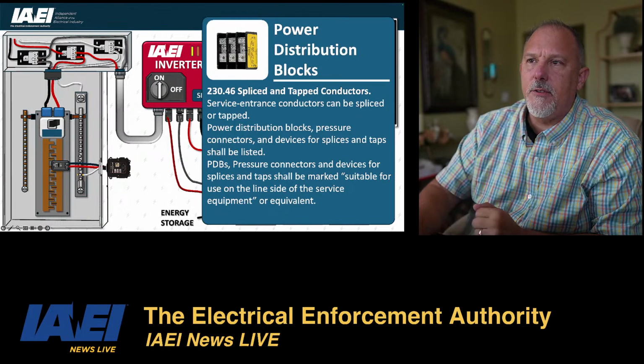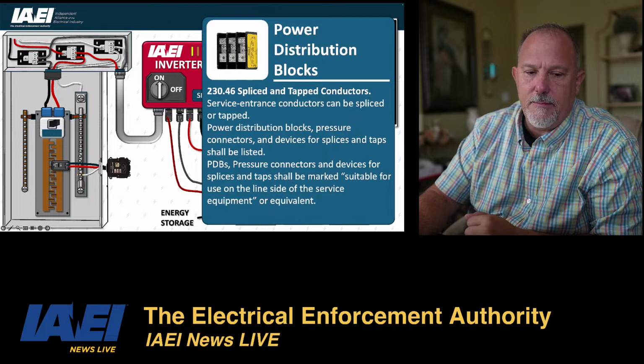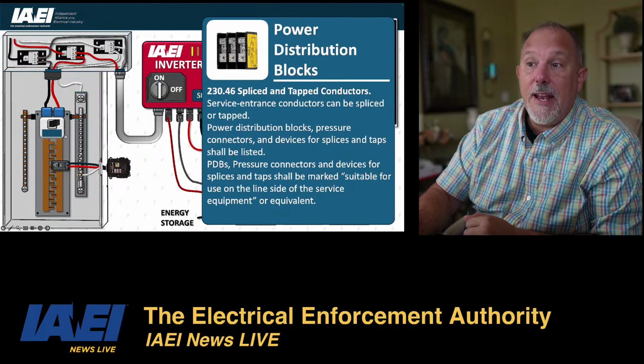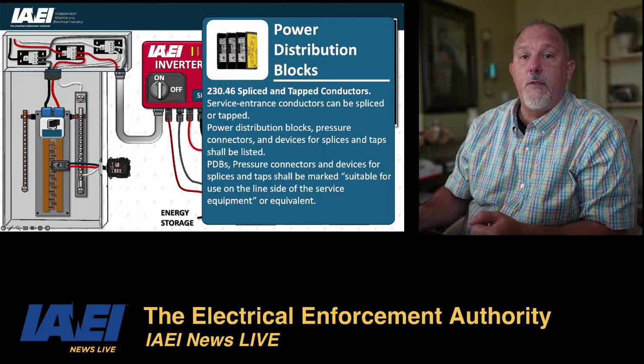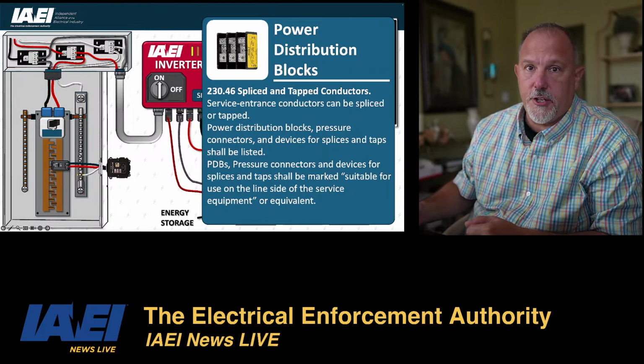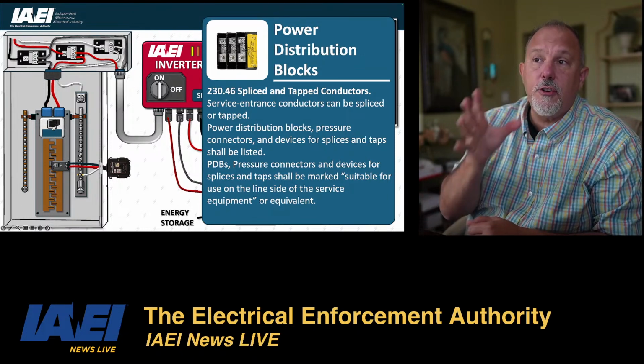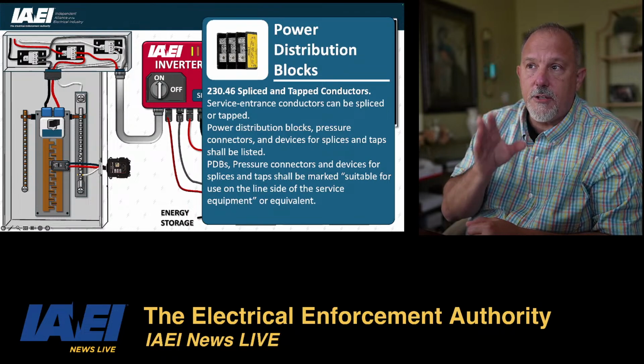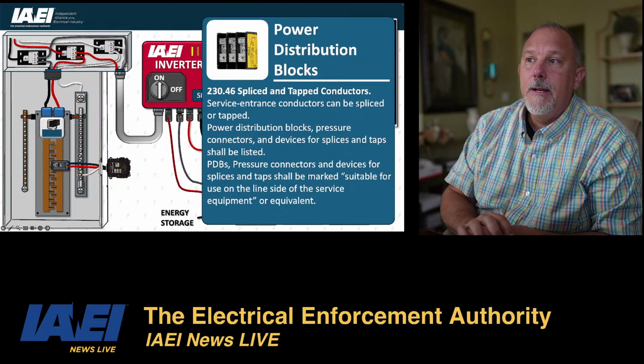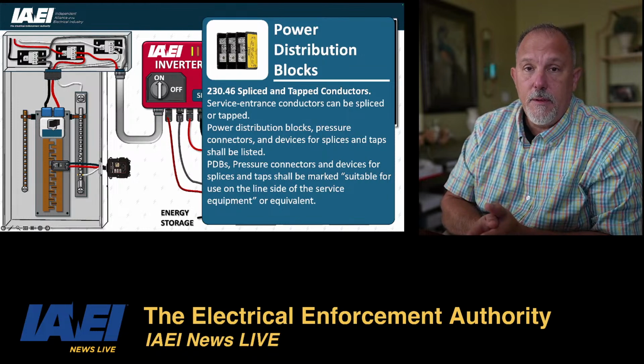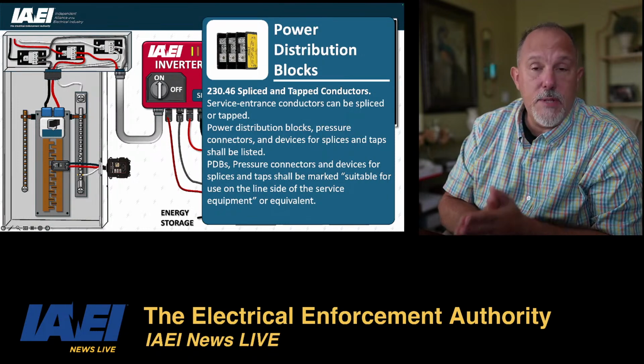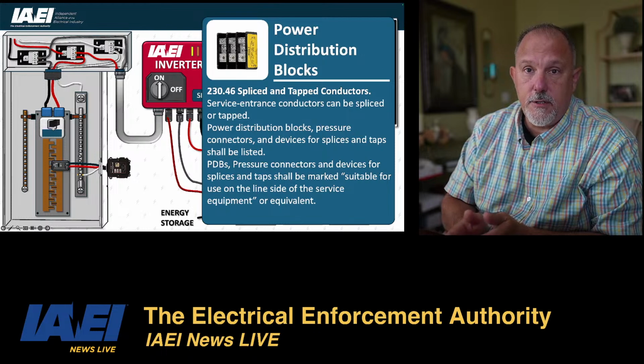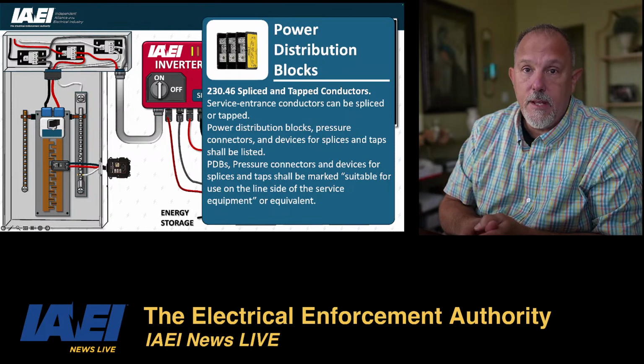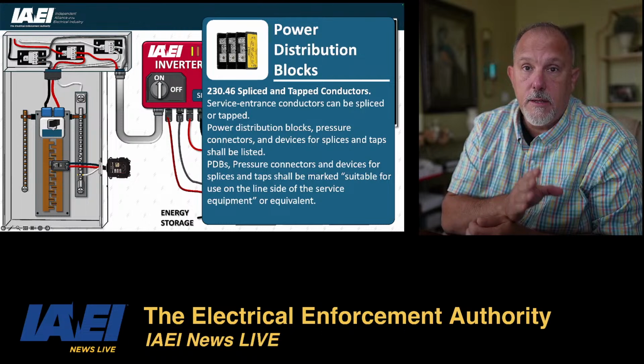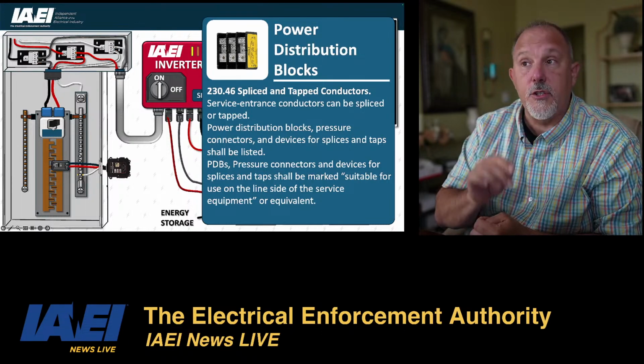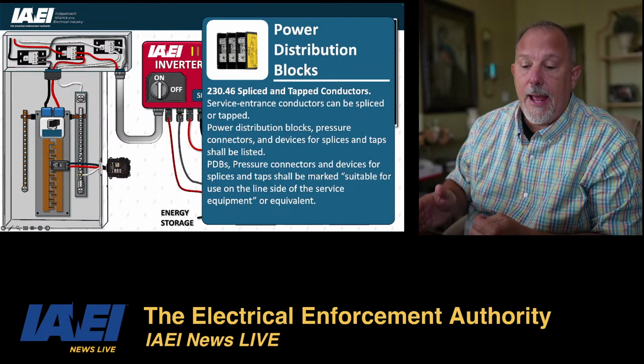So you think about these conductors as they come down through the system, they land on an overcurrent device. The downstream overcurrent device gives you your overload protection, but there's no short circuit protection for these conductors and those components. But what we do to limit the possibility of damaging those conductors is we put them in raceway. We protect them physically. That's our goal, is physical protection. So Article 230 has requirements for physical protection.